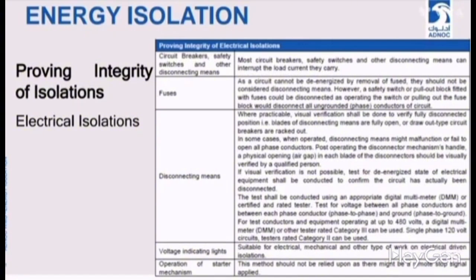If we need to send a stop signal from a remote area and shut it down, we will use all necessary measures while limiting these things. We will be able to ensure this when our people are working on any equipment, component, part, or device. At all times, we must ensure that our electrical isolation is 100% secure, safe, and blocked. The electric supply should be stopped.